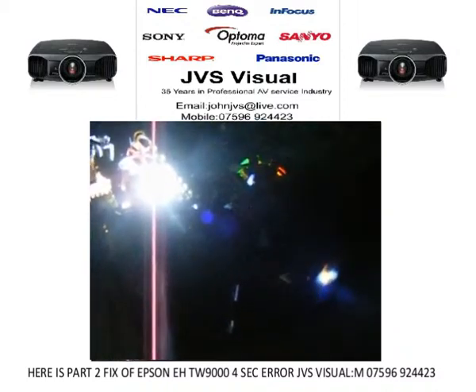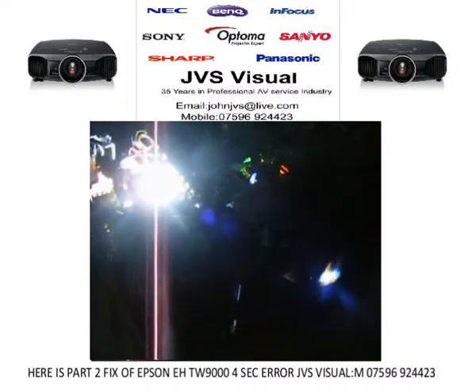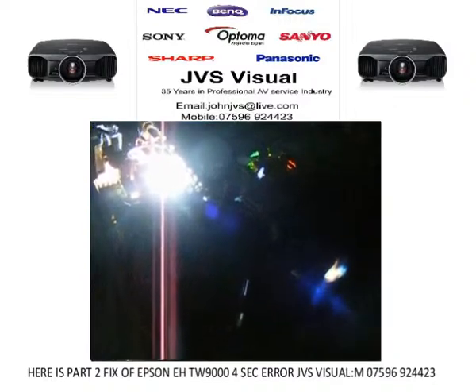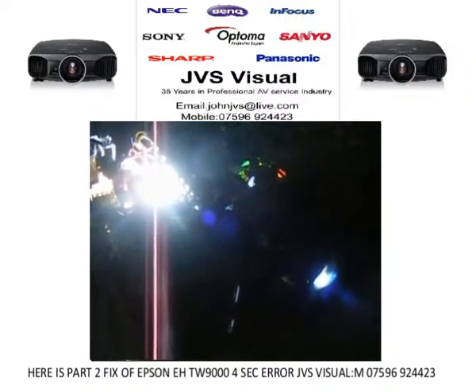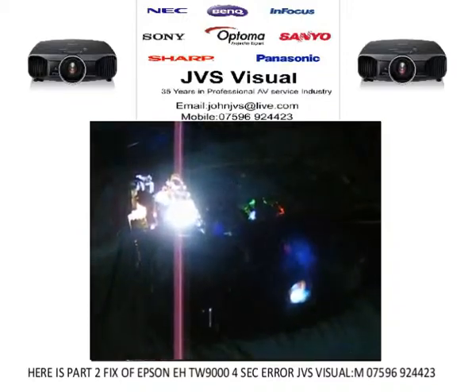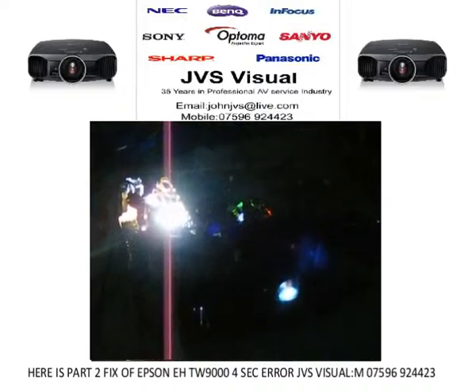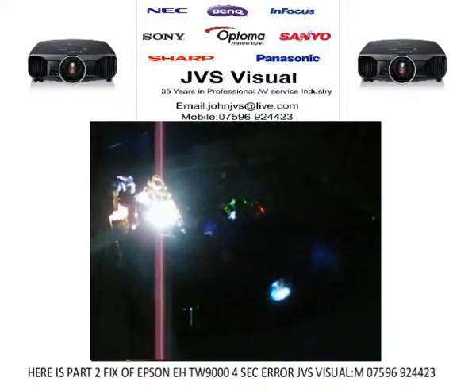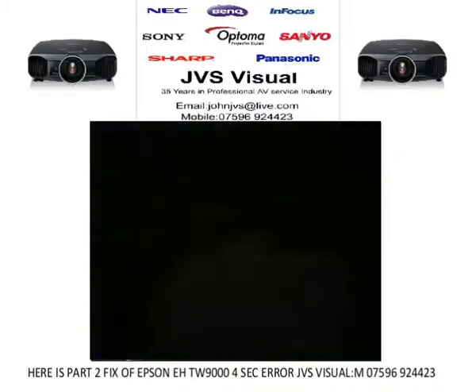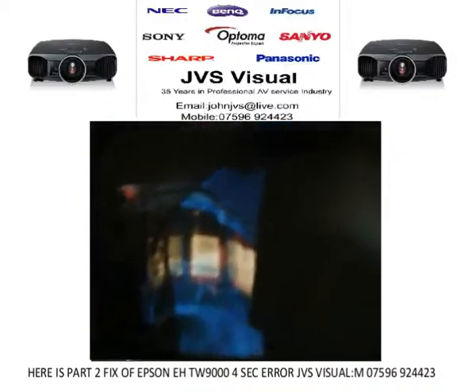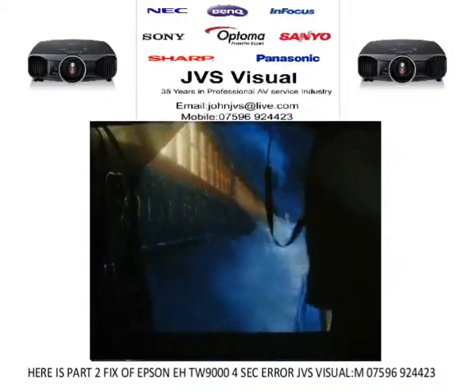Now, do you remember the TW9000? They had the 4-second count cancellation and then into error. Well, here is that beast. This is the TW9000. After 4 seconds of power up, the lamp would go out, the door would close. The only thing that would continue to run was the fan and the error codes. Okay, there it is, it's all up, and there's your image.